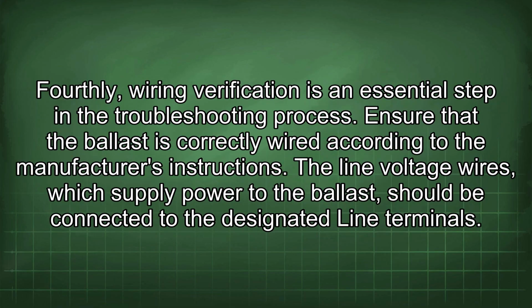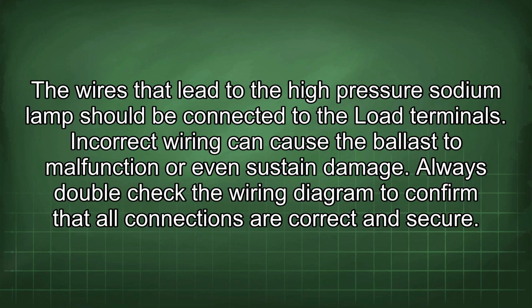Fourthly, wiring verification is an essential step in the troubleshooting process. Ensure that the ballast is correctly wired according to the manufacturer's instructions. The line voltage wires, which supply power to the ballast, should be connected to the designated line terminals. The wires that lead to the high-pressure sodium lamp should be connected to the load terminals. Incorrect wiring can cause the ballast to malfunction or even sustain damage. Always double-check the wiring diagram to confirm that all connections are correct and secure.